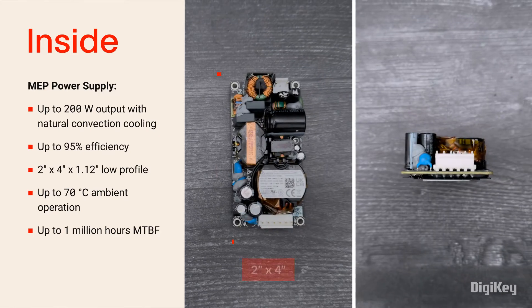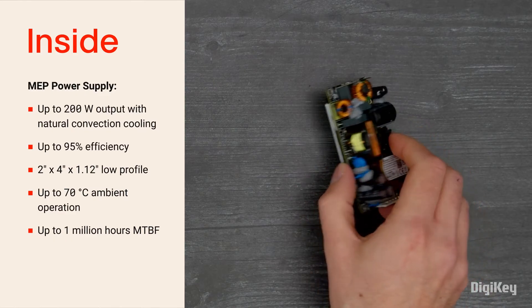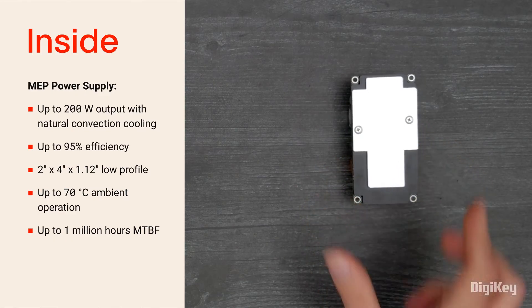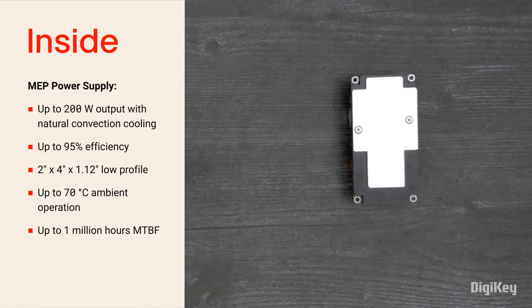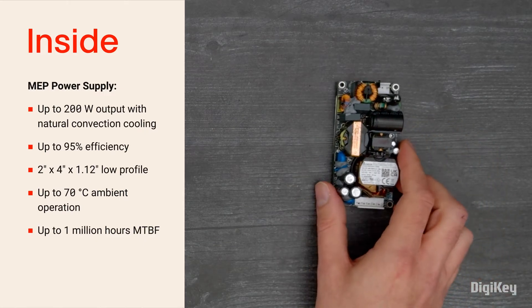The power supply has a two by four inch footprint and a 1.12 inch low profile. It's fitted with a heat sinking base plate, allowing the power supply to operate at up to 70 degrees Celsius ambient temperature with a one million hour MTBF.